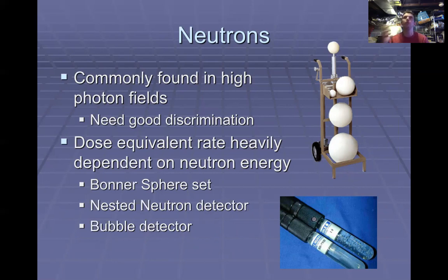So if you have neutrons, high energy neutrons in, say, like a LINAC vault that is covered in lead, they'll bounce off the lead, but because the lead atom is so much bigger, they'll bounce and just keep going. They won't lose a lot of energy. But if you have a lot of hydrogen present in something like water or plastic that has high hydrogen content, they actually bounce.